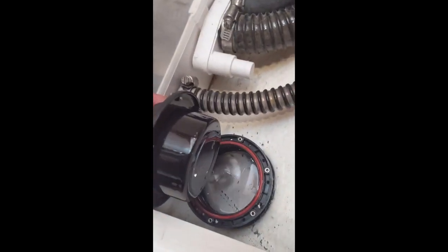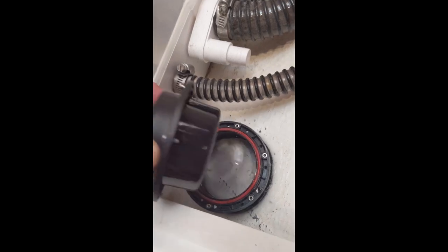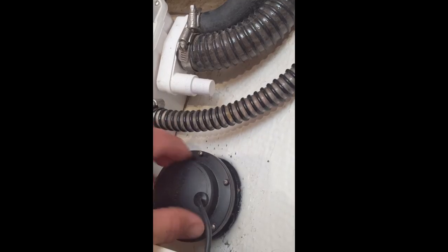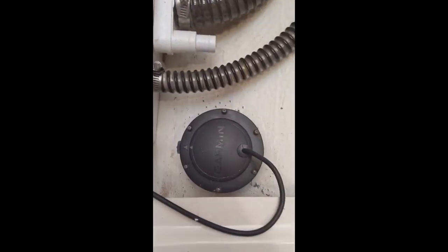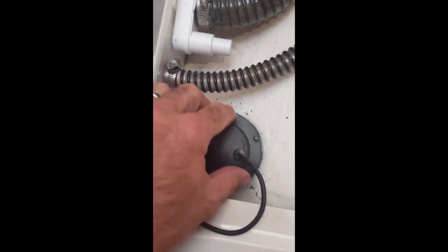Alright, we're done. So here is your area next to the head where the shower sump is, and your transducer I'm about to tighten back up and secure. I took the baby oil that you had in the compartment, and now this has been reseated. It's set up, seems to be holding fluid just perfectly as it should, and I'm going to tighten up the screws, and our transducer should be responding now. Yes, the transducer is responding once again.